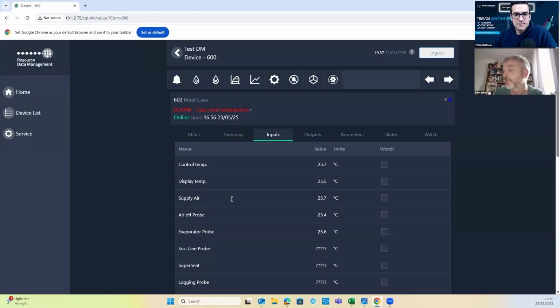If I'm really lucky, I can run in, grab hold of a probe and check it on the screen outside. If you go into the first menu on the controller, it shows you inputs and outputs. IO1 is control temp, IO2 is display temp, 3, 4, 5, and 6 are your probes. It tells you in the manual. And I can have a look and make sure the one I've expected has gone up. Yeah, it depends how good your electrician is, whether they put them on the right places or not. So I'm going to check that's working.